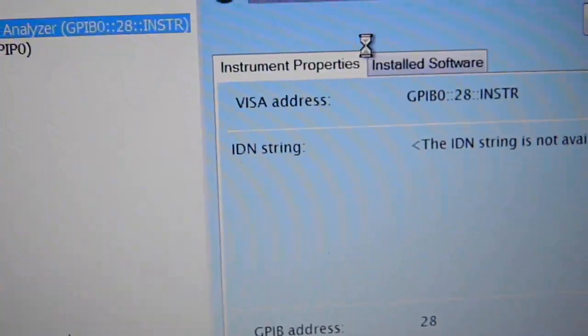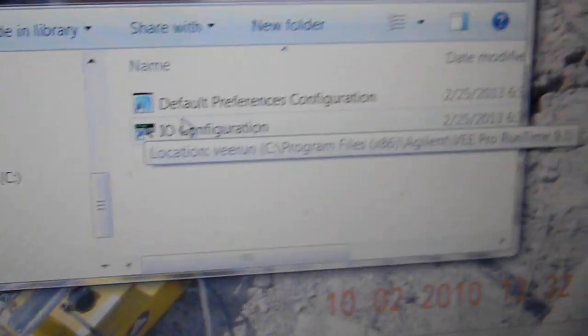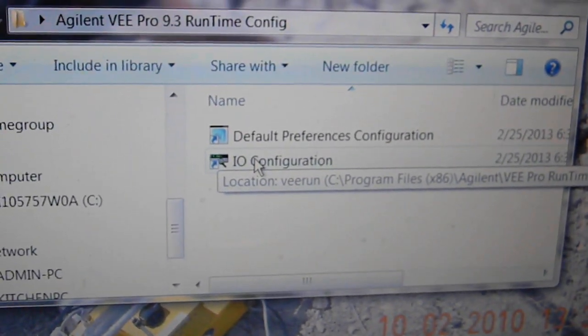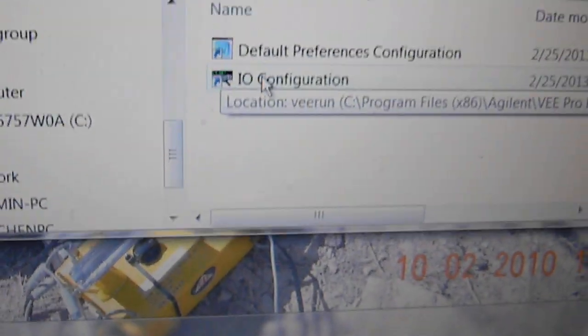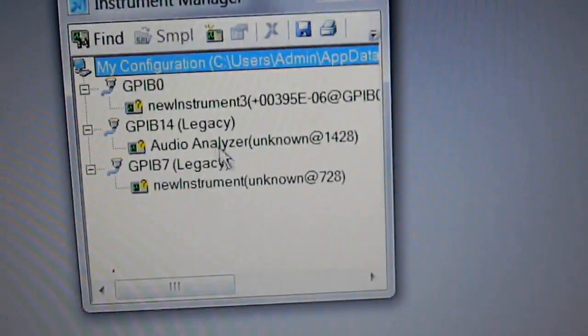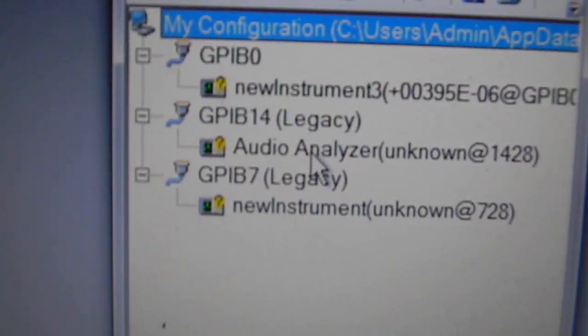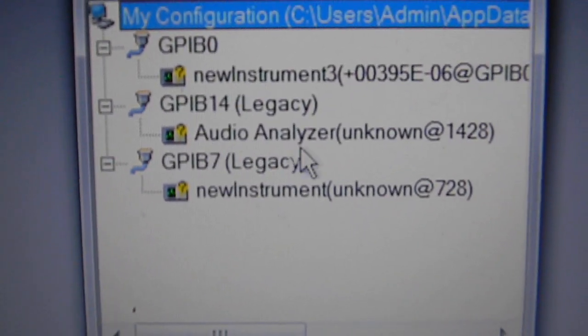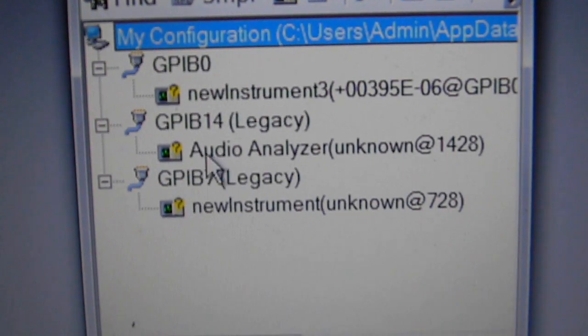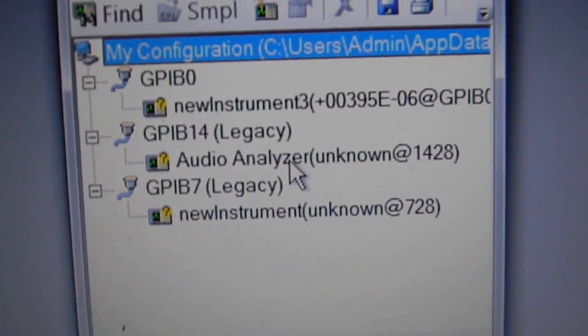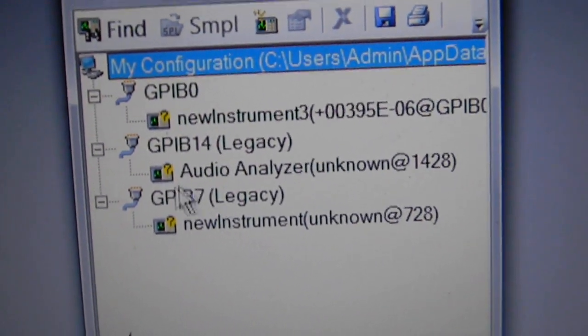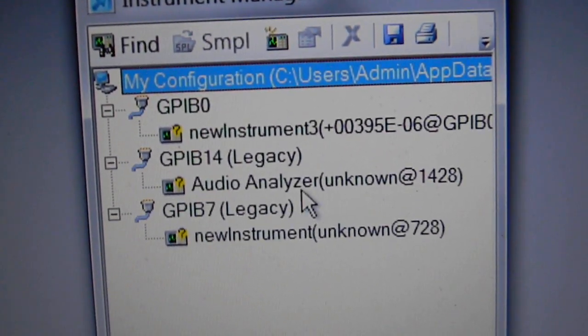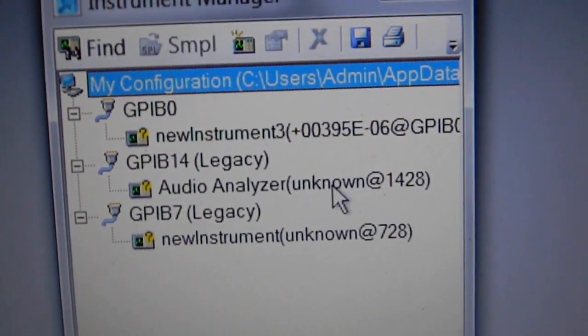Now there is the runtime program. The runtime program, which is the VEE Pro 9.3, you get that off of the Agilent site too. If you do the IO configuration in here, this is the one right here that you've got to change. I had to change this one. I renamed it to Audio Analyzer because I was getting some errors that says Audio Analyzer Not Found.